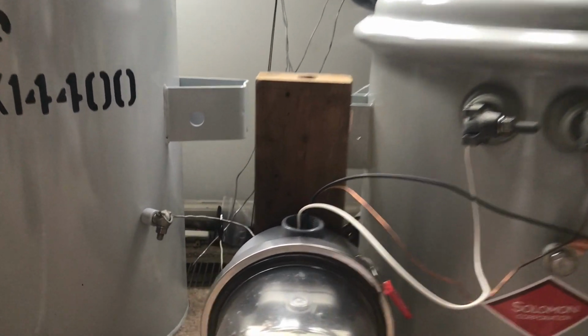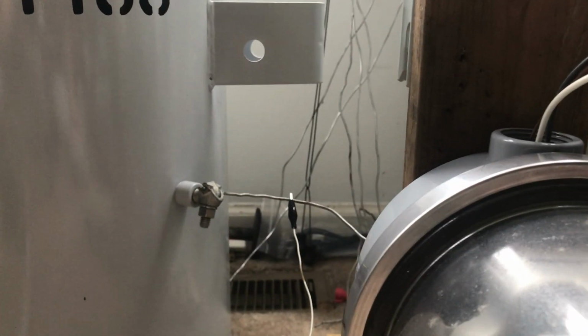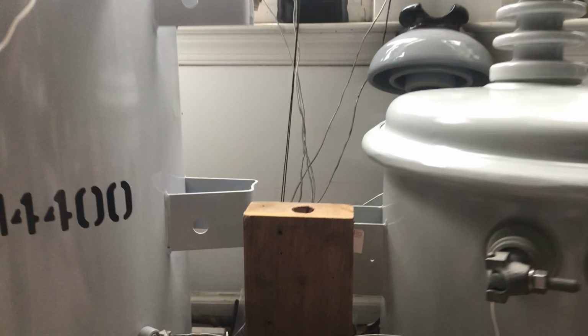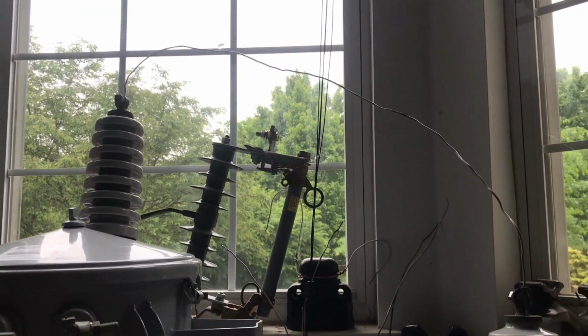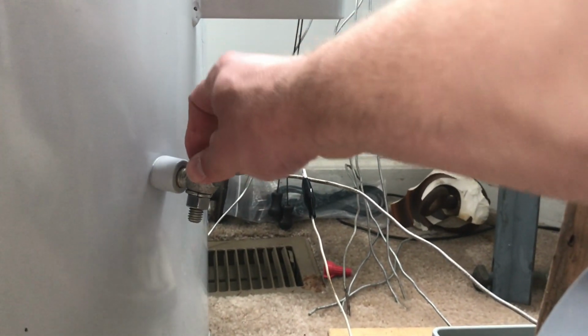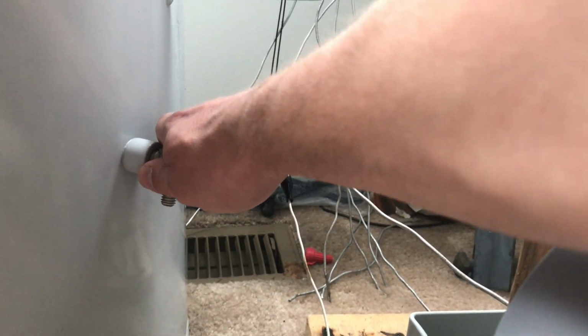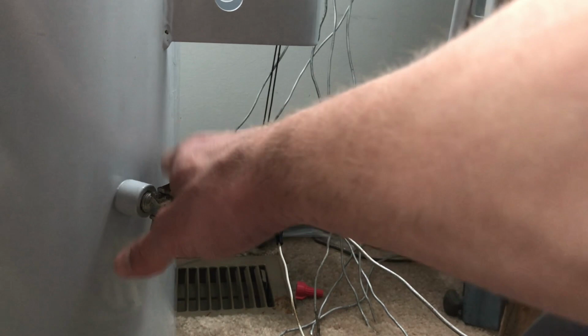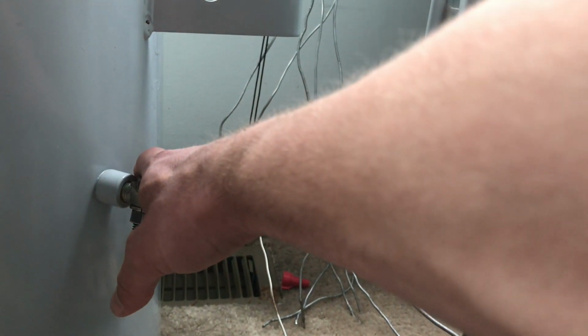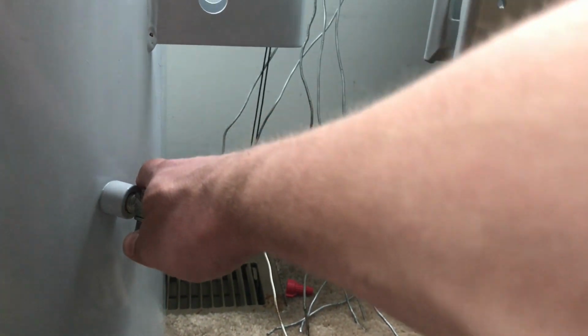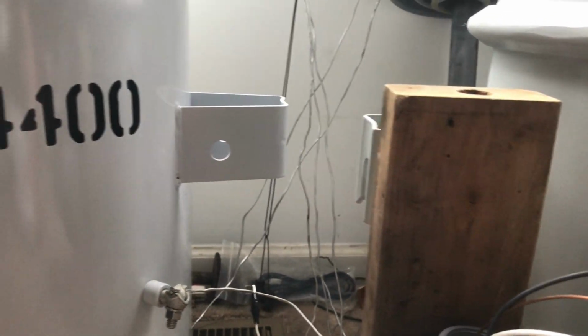Now, I know I'm going to get dinged for saying neutral and ground interchangeably. However, on the distribution side of the world, neutral and ground are the same thing. This on a Y system is always at ground potential, and it's the neutral. It is also a current carrying conductor. Unlike in a residential system, the ground is not a current carrying conductor.